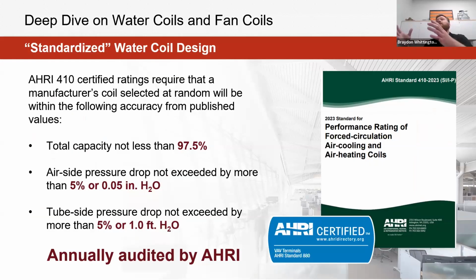So any of you that may have installed a water coil in the field or seen some of these products, commonly you're going to see this blue label on the coil itself, essentially saying that it has been rated and certified to this AHRI program, which evaluates that the published performance from that manufacturer, or through that software, is what you're going to be expecting. It's a pretty stringent program in terms of how in line that capacity needs to be for that coil, and also some of those pressure drop characteristics, so your fluid side as well as your air side pressure drop for that equipment too.